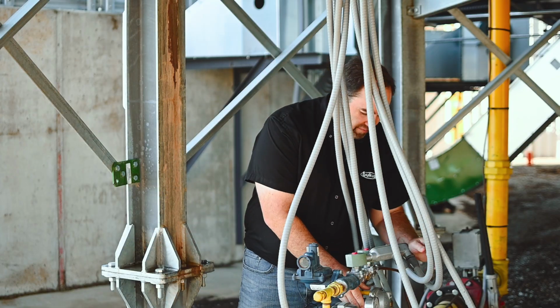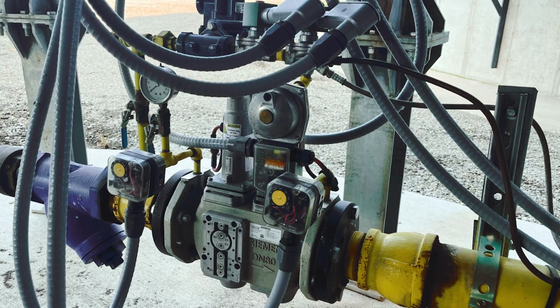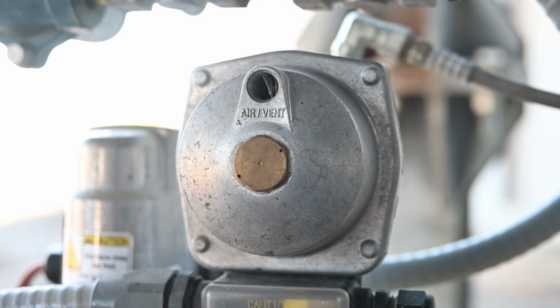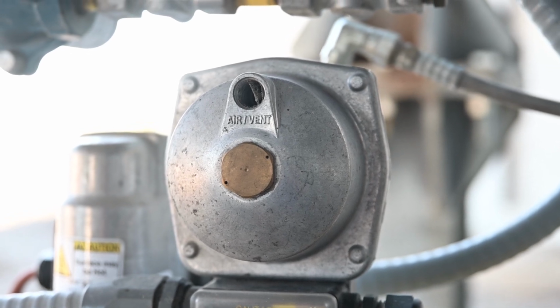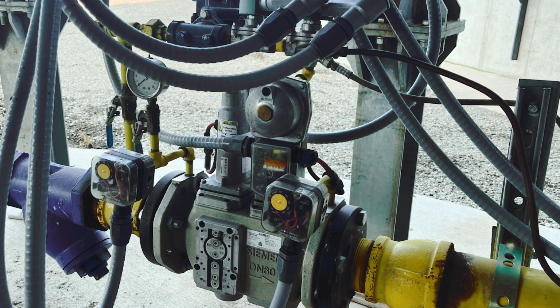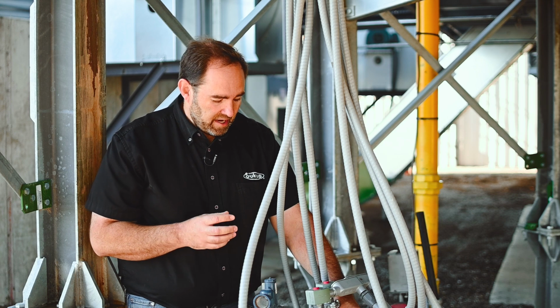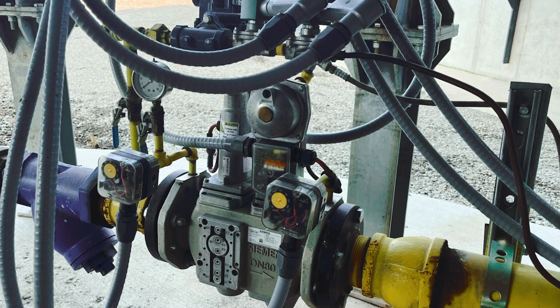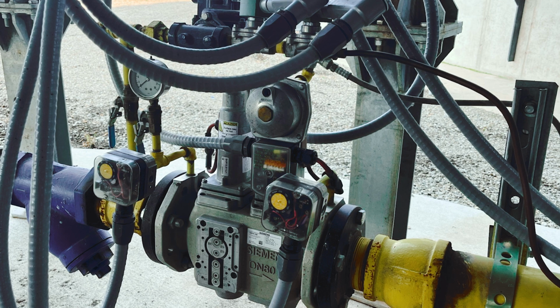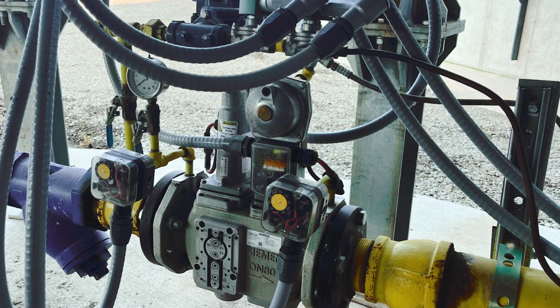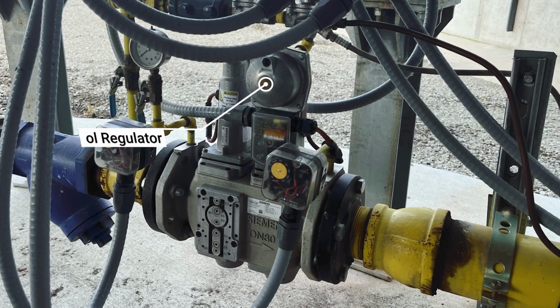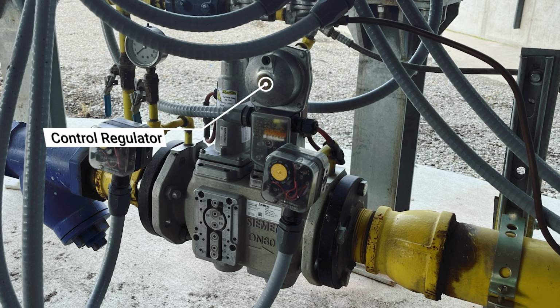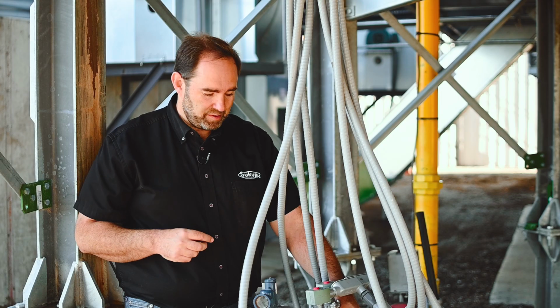The second safety valve is actually a valve with a regulator built into it. The regulator is the control regulator that controls how much pressure goes up to the burner. So it's dual purpose: the valve is on-off, just a second safety valve in line, and then there's the pressure regulator, which can be adjusted by removing this cap here, and then you have a typical flathead adjustment in there. That regulator determines what the control gas pressure is downstream. It would be set at 40 inches of water column with the butterfly valve wide open. We'll look at that when we see the butterfly valve.